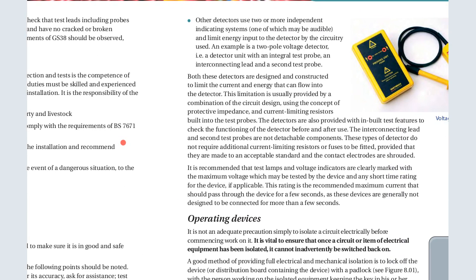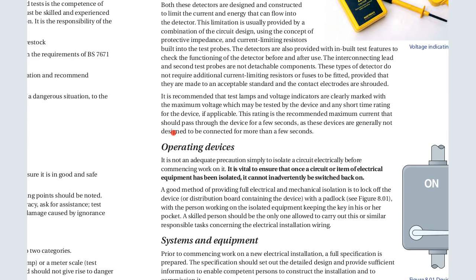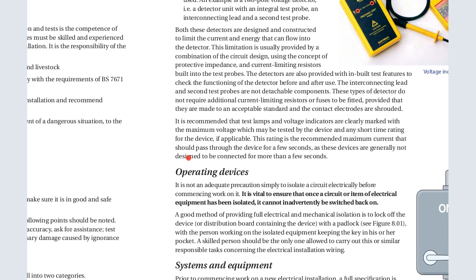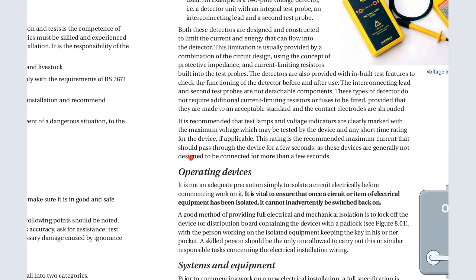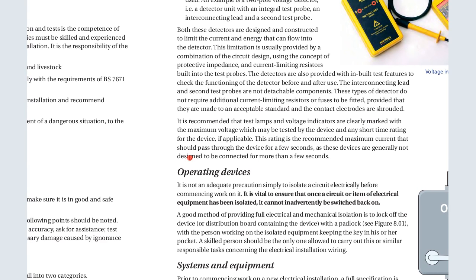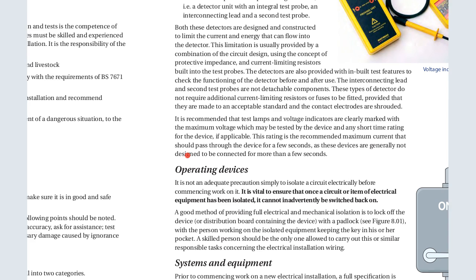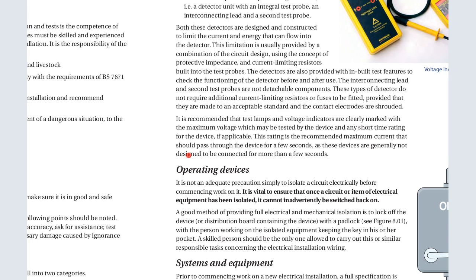Now, other detectors also use two or more independent indicating systems, one of which may be audible, and limit energy input to the detector by the circuitry used. An example is a two-pole voltage detector, i.e., a detector unit with an integral test probe and an interconnecting lead and a second test probe. So both these detectors are designed and constructed to limit the current and energy that flow into the detector. This limitation is usually provided by a combination of the circuit design using the concept of protective impedance.